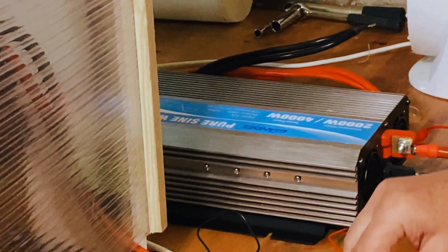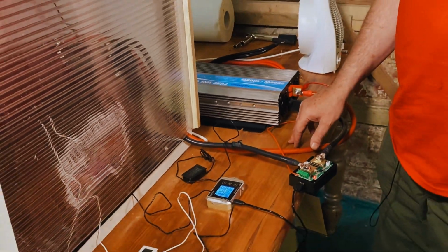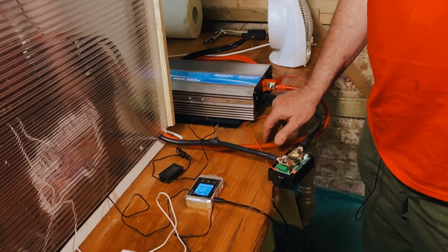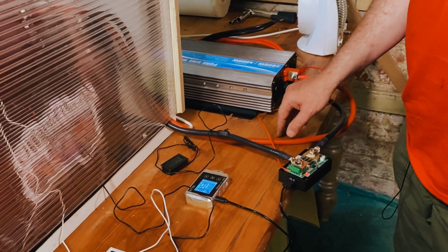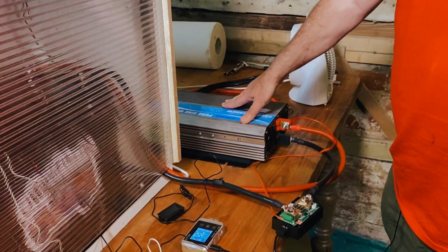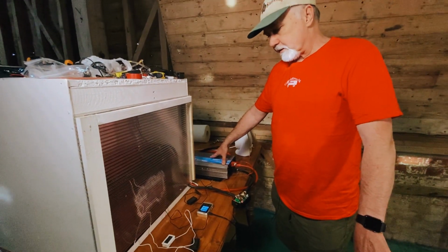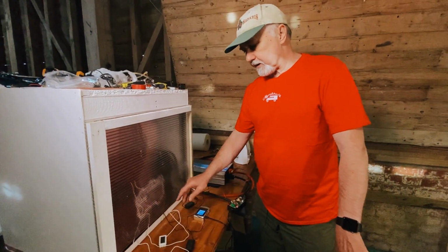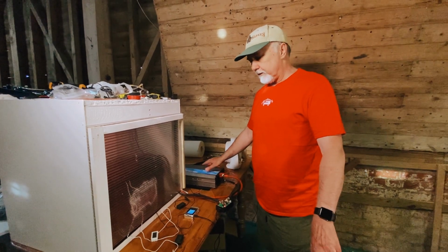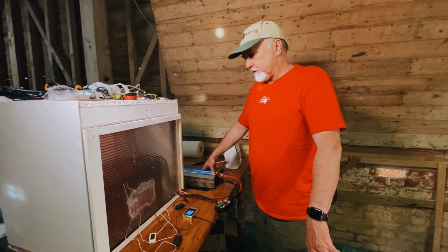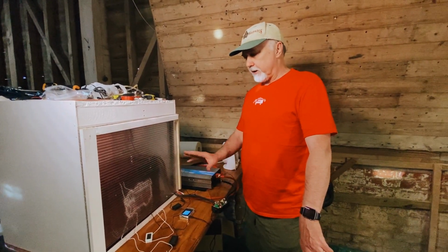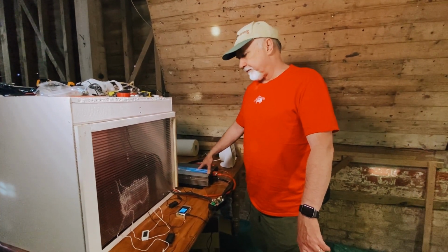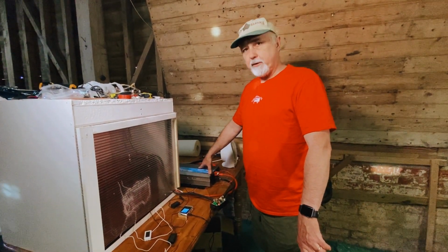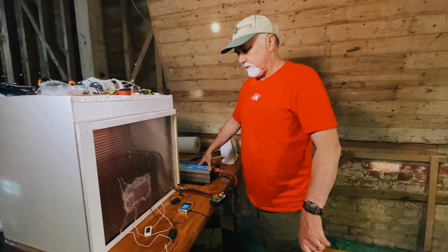Used up 155 amp hours so far of a 280 amp hour battery, so it's going well. We're going to stop the test now because the purpose was to run a very heavy load for an hour to see how the battery would cope in terms of temperature. Not much point continuing, it will continue to rise.